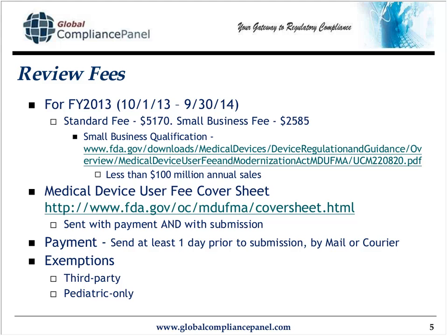When it comes to review fees also, you've got to fill out a medical device user fee cover sheet. And when you send your $2,500 or $5,100 in advance of your 510K, with the payment, which goes to a different location than the submission itself, you're going to identify your company and your small business number on the user fee cover sheet. I recommend that when you send the payment, you send it a full day prior to submission.